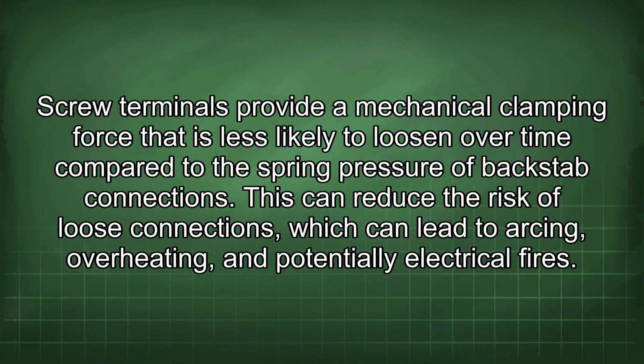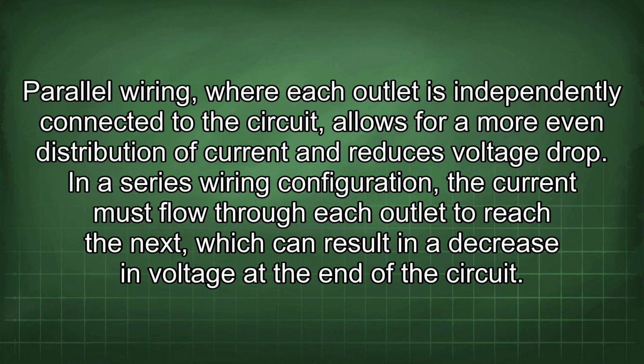Screw terminals provide a mechanical clamping force that is less likely to loosen over time compared to the spring pressure of backstab connections. This can reduce the risk of loose connections, which can lead to arcing, overheating, and potentially electrical fires.